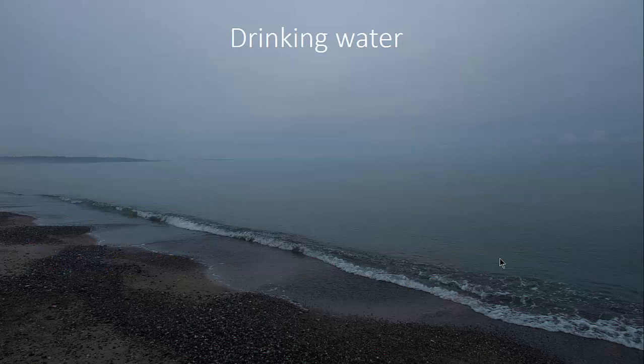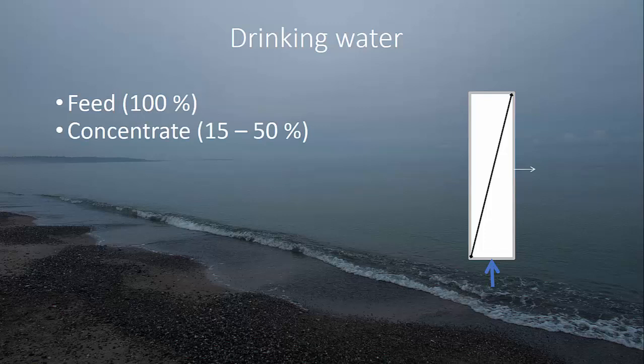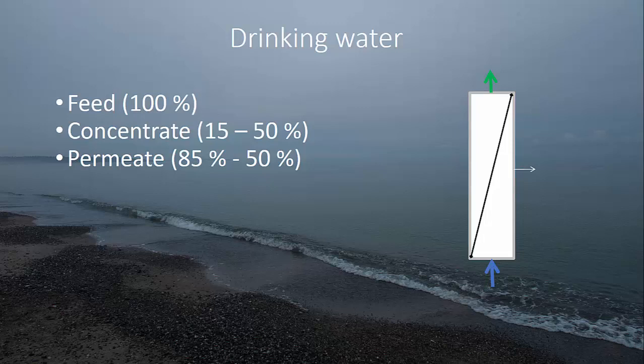Looking at drinking water: the membrane, shown as a black line, separates what we want to remove from what we want in the drinking water. Normally you have a feed of 100% pumped into the membrane. You then need to remove the concentrate, which contains the things you don't want in drinking water. How much concentrate depends on the water source — for a desalination plant it could be as much as 50% concentrate, while for fresh or lake water you might get away with 15%. The permeate stream is what produces your drinking water; the more concentrate, the less permeate.